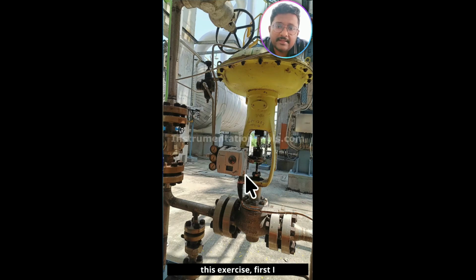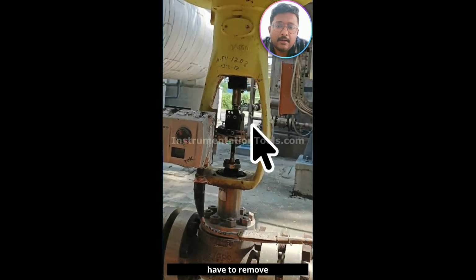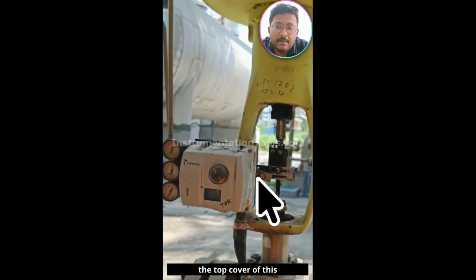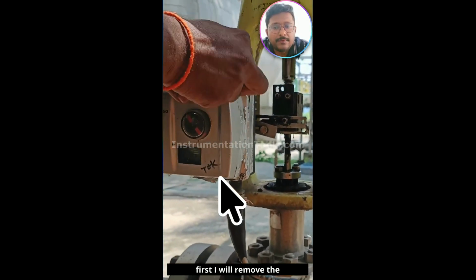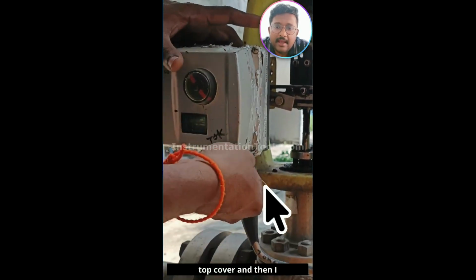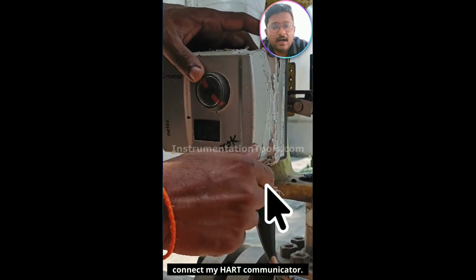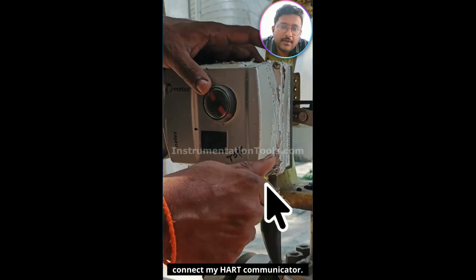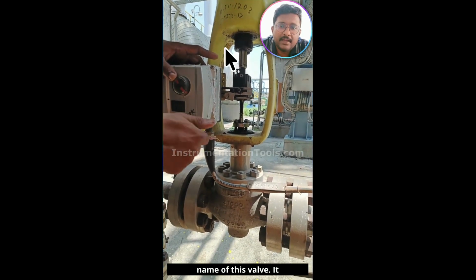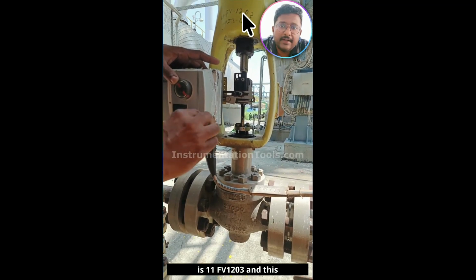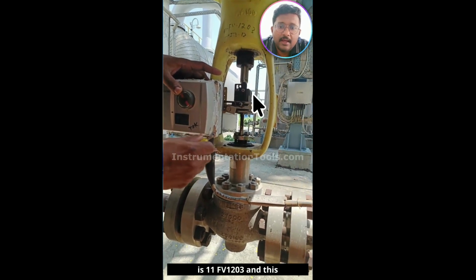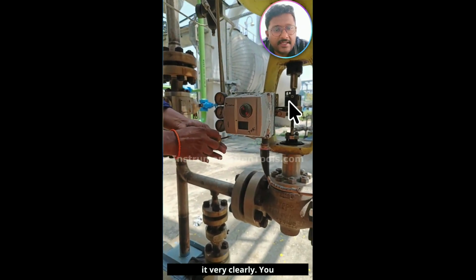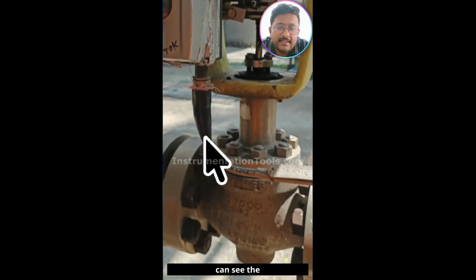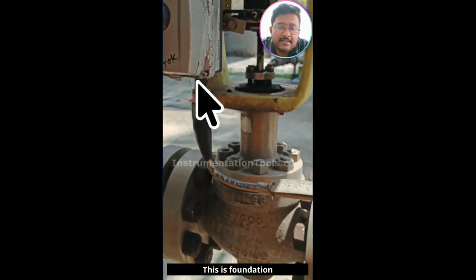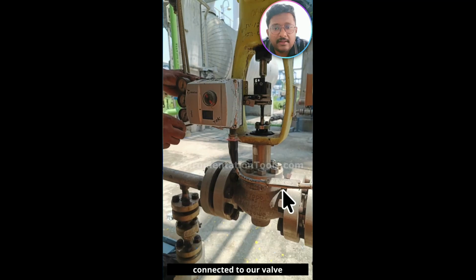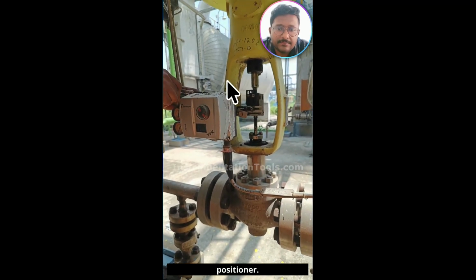Now to do this exercise, first I have to remove the top cover of this valve positioner. So first I will remove the top cover and then I will connect my HART communicator. You can see the tag name of this valve. It is 11FV1203 and this is the valve stem. You can see it very clearly. You can see the orange color cable. This is the foundation fieldbus cable connected to our valve positioner.